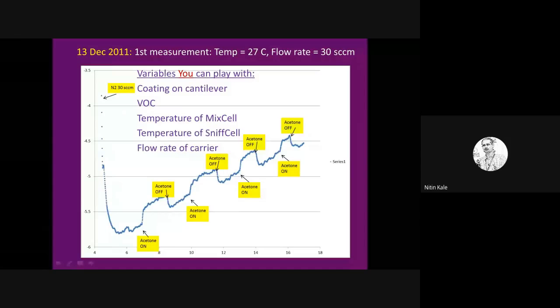This is the second thing. Third thing is that you have seen a drift. This drift is in the electronics. We have corrected this, so it can actually look something like this. Okay, a straight line now, parallel to the x-axis. The drift has been removed. Why I like to show this graph is, this is the first time we did this experiment, about 9 years back, and we got everything right, this result itself, the very first time in such a complicated setup.